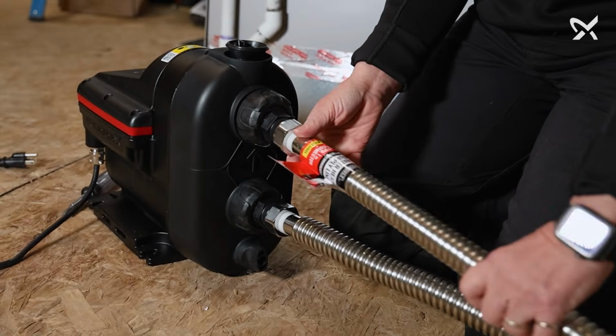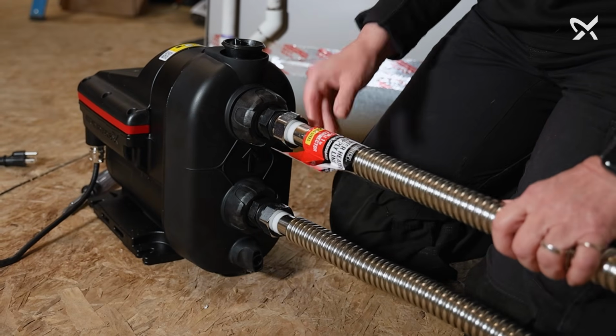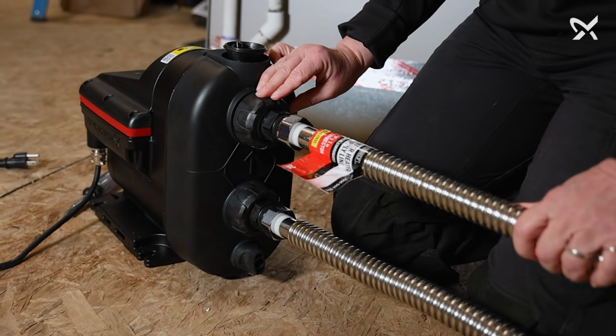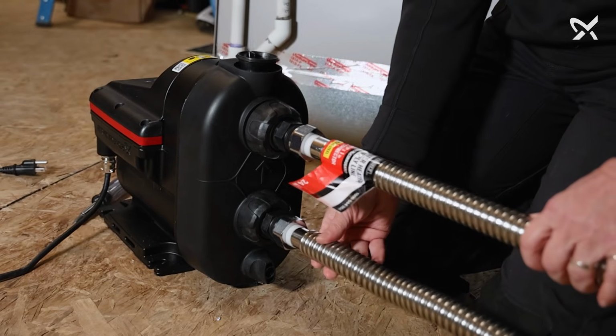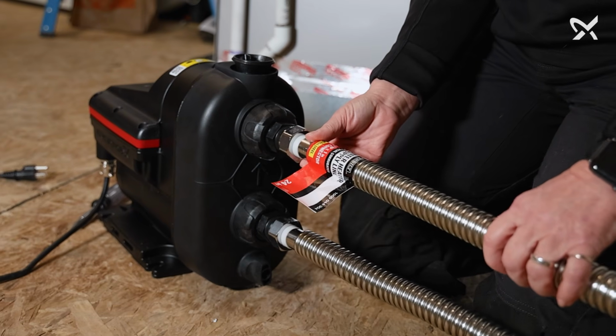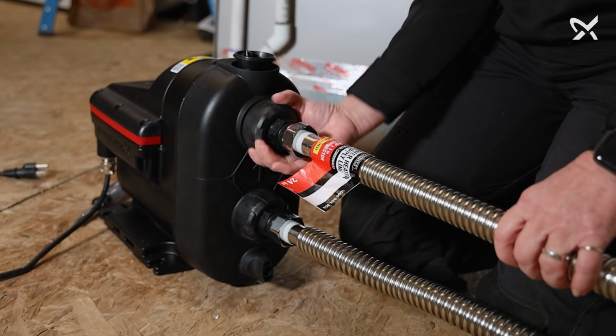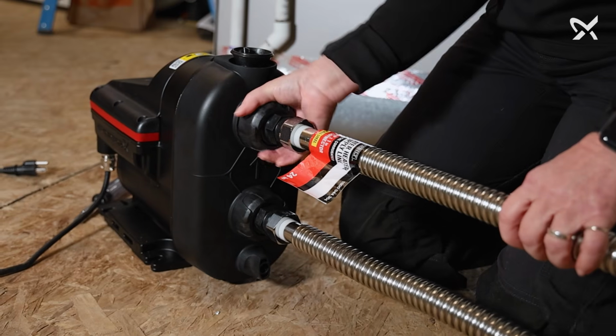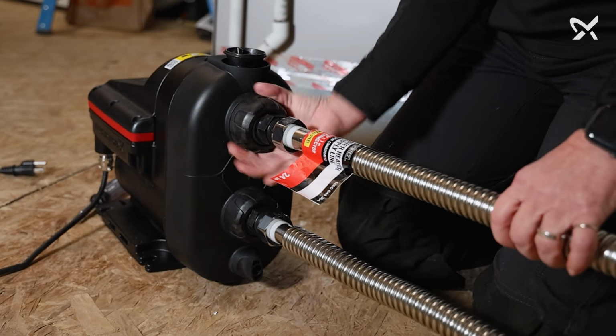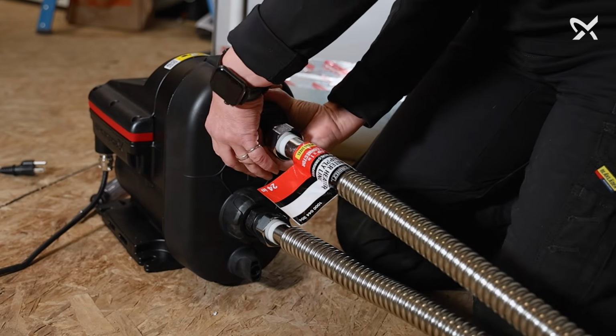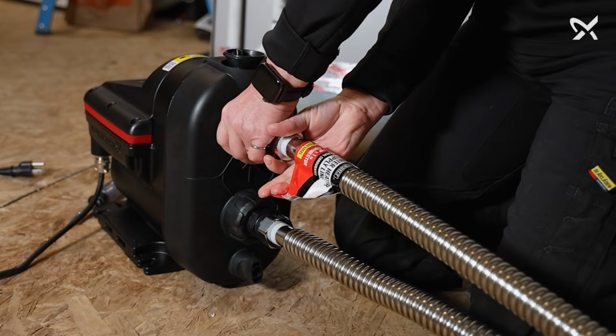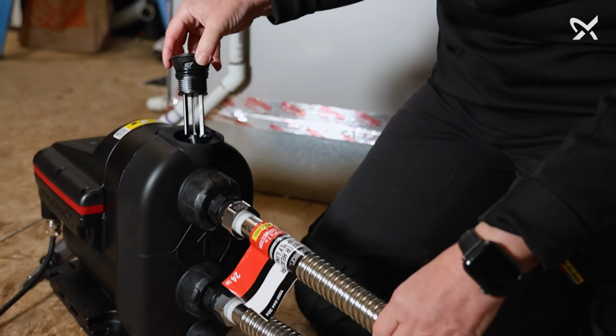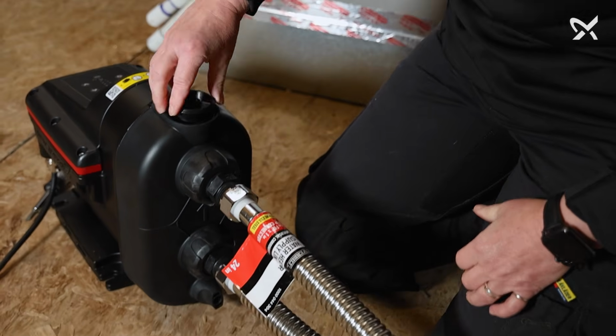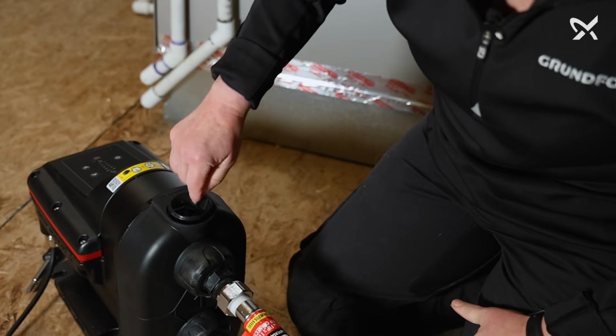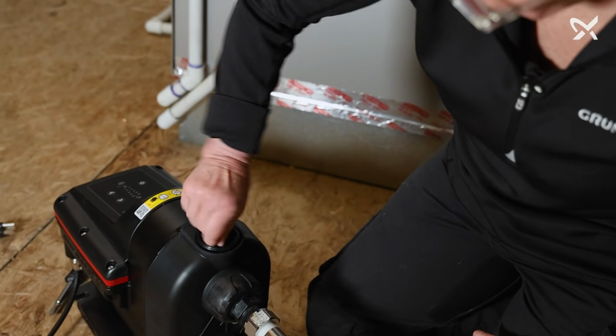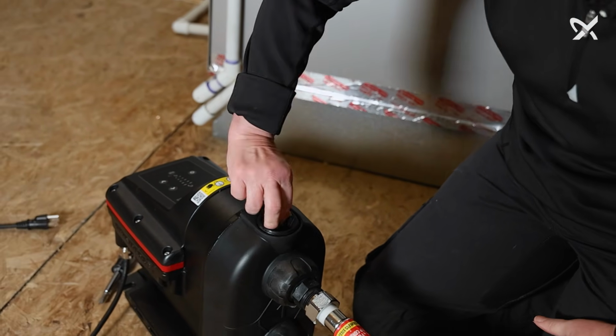Aside from the PVC threads that connect to your flex connectors, we also have those unions where the swivel takes place. It is important, do not put a wrench on those union connections. It's hand tighten only. Okay? There's an O-ring that can be damaged, so you want to tighten the union connections at the swivel by hand and also the priming port. All of these have an O-ring seal. They don't require a tremendous amount of torque, so don't put a wrench on it, even though you may feel tempted to do so.